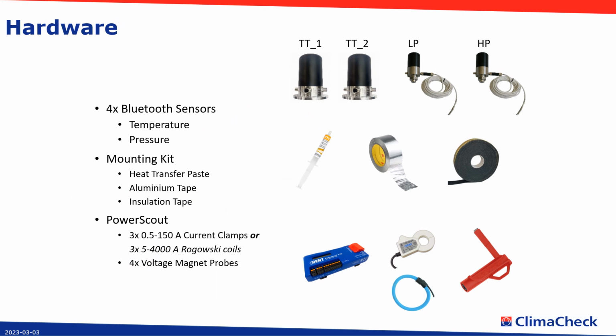This is the available hardware for the ClimaCheck Lite. The two Bluetooth sensors labeled TT1 and TT2 can be connected to 3 temperature sensors each. The low pressure sensor has a pressure range from 0 to 10 bar gauge and can also measure 1 temperature. The high pressure sensor has a pressure range from 0 to 35 bar gauge and can also measure 1 temperature.